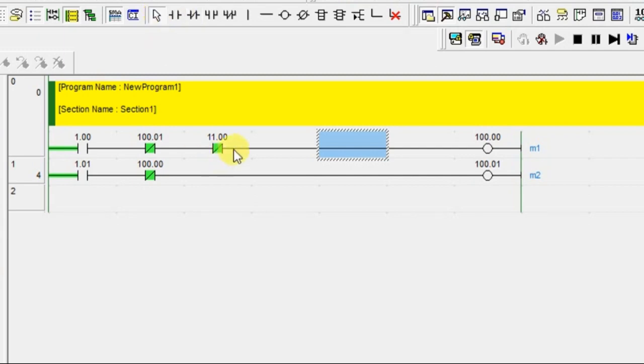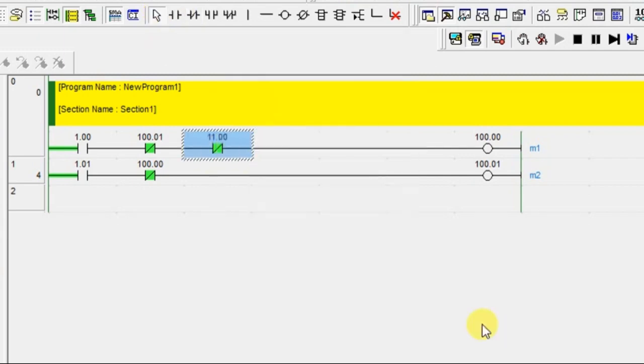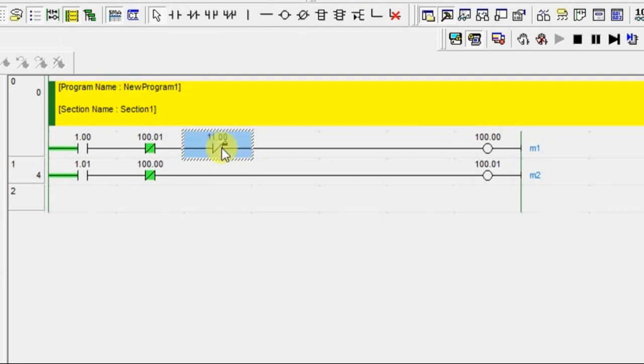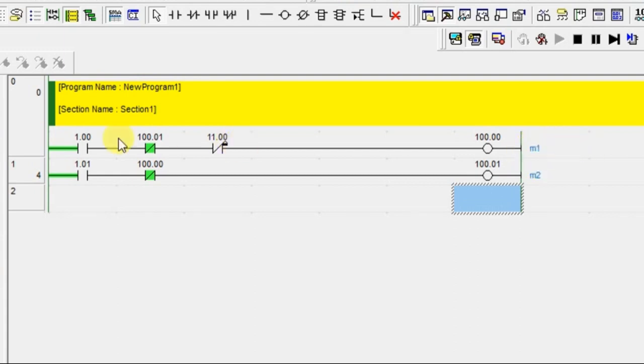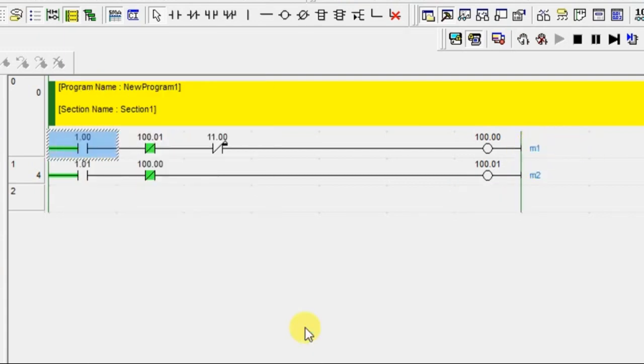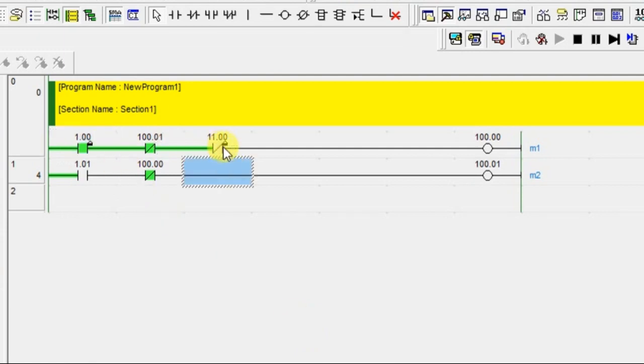Someone is using this 11.00. Let us take this is one of the alarm conditions. Alarm is there. In that condition, someone is trying to turn on motor 1. They are trying to turn on the switch. The switch is on. But since the alarm is there, it is not allowing the motor to be in on condition. This is interlocking.